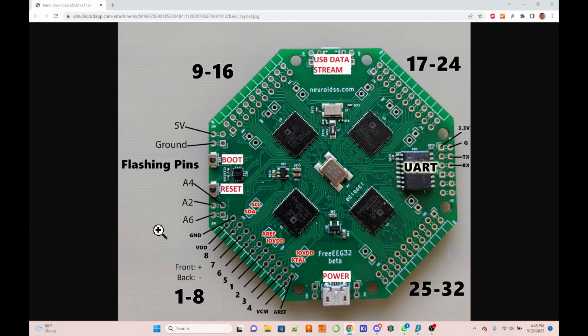The way to consider the difference between this system and the SRB2: every single channel on this board has 2 pins, a positive and a negative pin. The positive pin goes on the location where you want to measure, and then you have to place the negative pin elsewhere. Consider these 32 channels that we have. Each of them is like a voltage meter, like a multimeter where you measure the power of a battery, except it does it 512 times per second with 200 nanovolt precision.